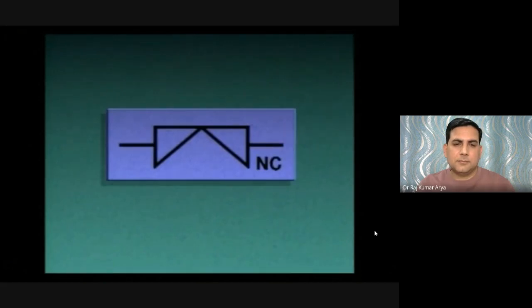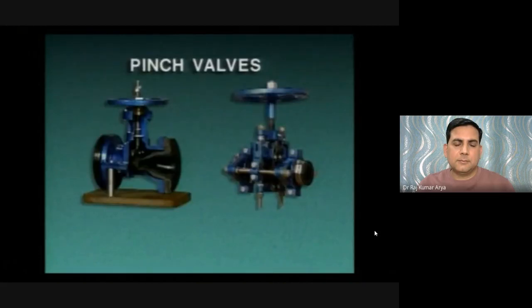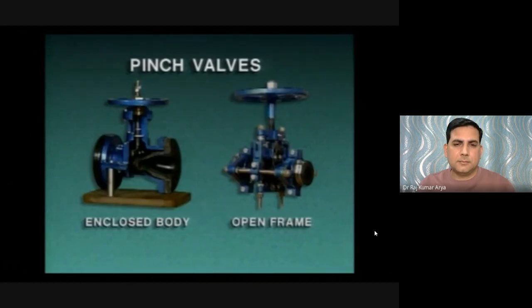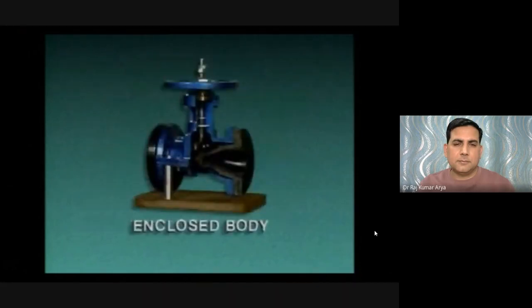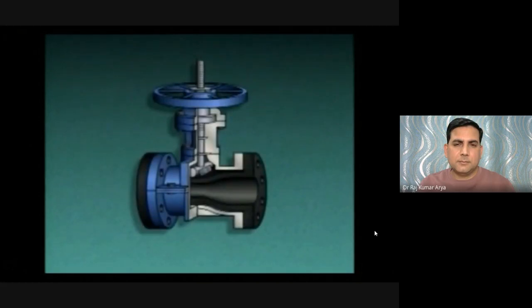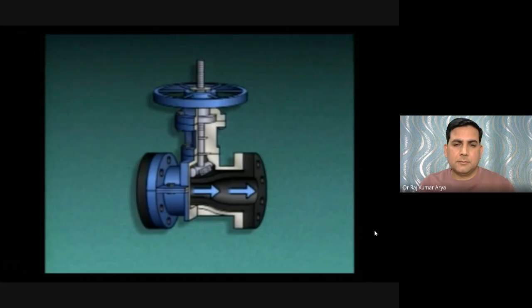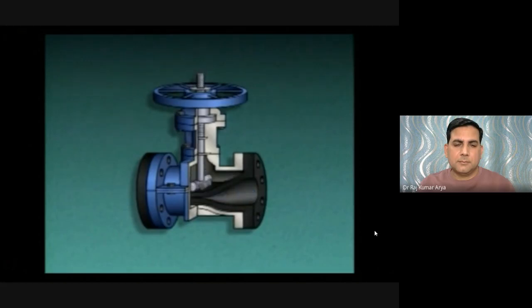Pinch valves are sometimes used to control the flow of heavy sludge and slurries. They come in two basic types: enclosed body pinch valves and open frame pinch valves. An enclosed body pinch valve has a cylindrical body, and consists of a stem, a hand wheel, a bar or clamp, and a flexible tube through which fluid flows. As the hand wheel is turned to close the valve, the stem pushes the bar against the tube, squeezing or pinching it to stop flow.